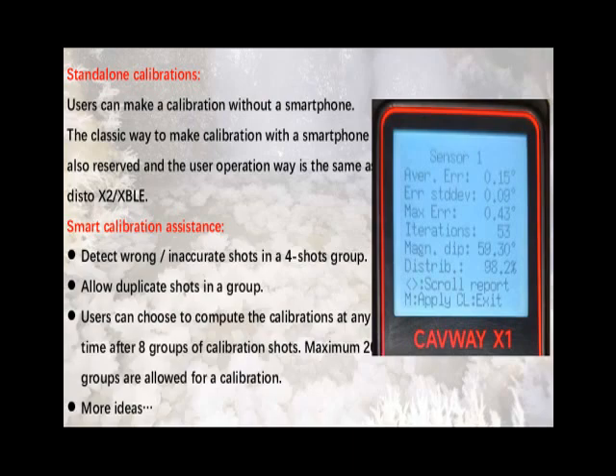After making 8 or 14 groups of calibration shots, users can press upgrade to let the new device calculate a new set of coefficients. Or users can choose to download all the calibration shots to an application on a smartphone, calculate the coefficient there, and upload the coefficient back to the device. Both ways are supported.